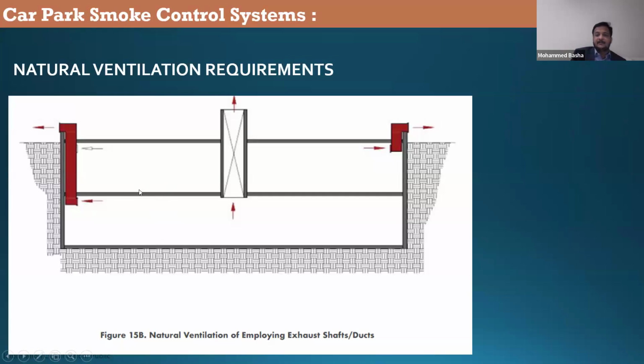Whereas in the bigger car parks, there will be a larger number of people. So the behavior of the people will be different, the crowd will be different. We call this crowd management. If the number of occupants is more, the behavior of the crowd, everything is going to be different. There, you cannot expect natural ventilation to give you sufficient tenability. That is the reason basically. So if your client doesn't want natural ventilation, you should still go for mechanical smoke extract, or if the civil defense feels that it is required, you still have to go. It's an authority having jurisdiction requirement, but we have an option in QCD.